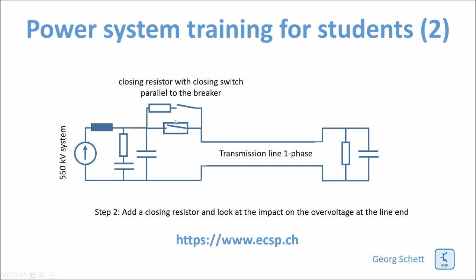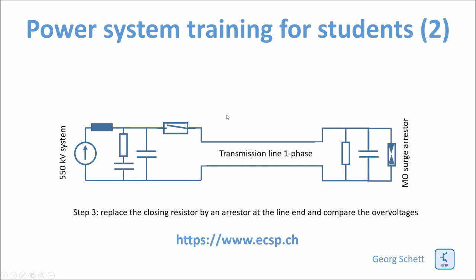The scheme with the closing resistor is relatively complex. And therefore it is preferred if possible to, instead of having a closing resistor, to just add an arrester at the line end. Let's see how this works. I have now added a surge arrester at the line end. And let's now set the parameters of the surge arrester.